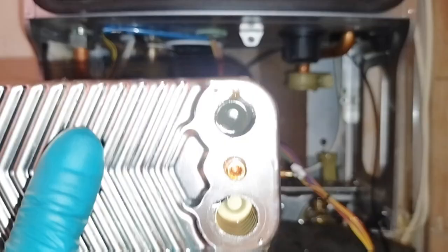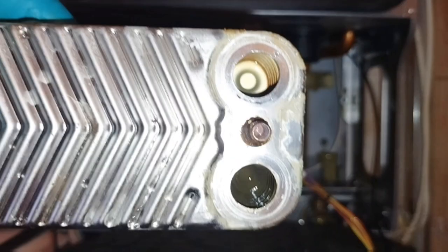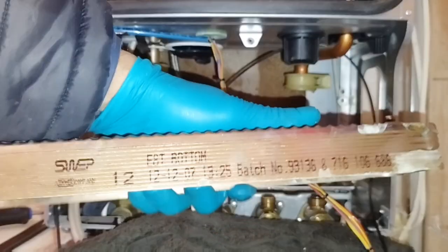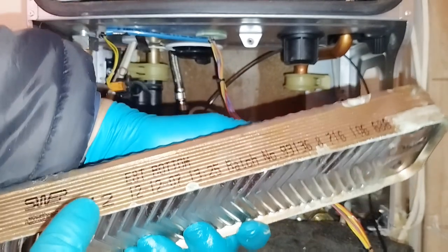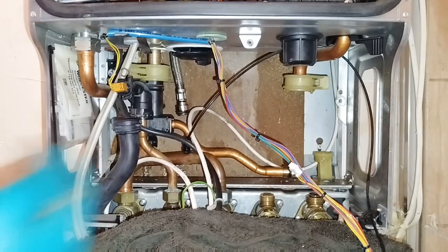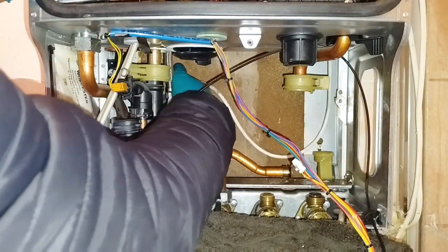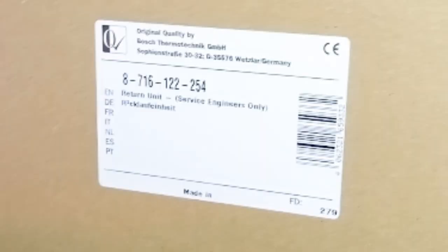As you can see, where the heating water passes is literally blocked with black rust, and it's discolored into black. Alright, so we'll place the plate heat exchanger aside. This is a 12 plate, as you can see, the 12 where I'm pointing at the moment, it's a 12 plate heat exchanger. So I've just checked that the washers, the O-rings for the plate heat exchanger are still in place.